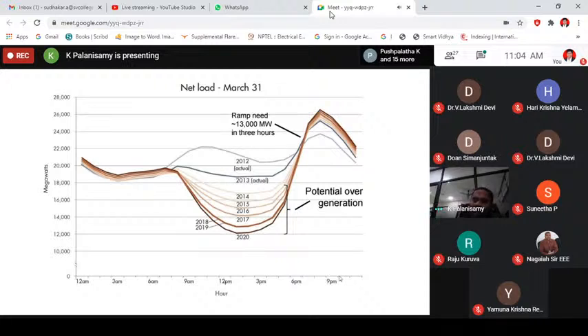And this is actually the California curve. See, the curve is plotted from 2012 data to 2020. In 2012 this is their load curve, something like this. But slowly, when they started to increase rooftop solar PV panels, the load curve is coming down. It means the power drawn from the central grid is coming down. By 2020, we can see around 8,000 megawatt of power requirement is reduced.